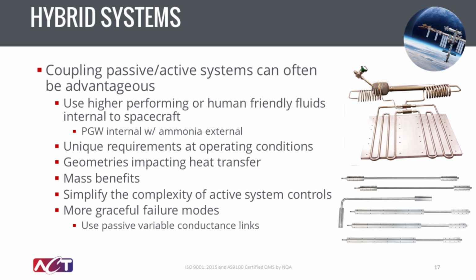Also, again, there's ways for complexity to be greatly simplified if you don't have to route unique fluid geometries all over the place. So oftentimes we can use a more simplified single-phase loop to reduce the risk associated with failures in a single-phase loop, and then a more complex passive loop with loop heat pipe or constant conductance heat pipe technology to transfer heat out to the radiators and reject to deep space.